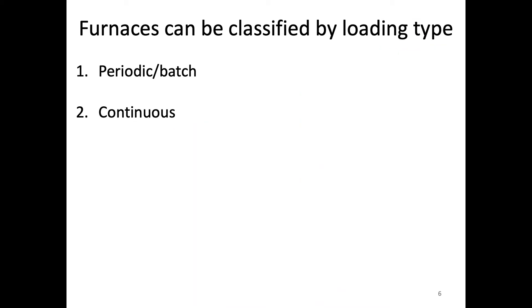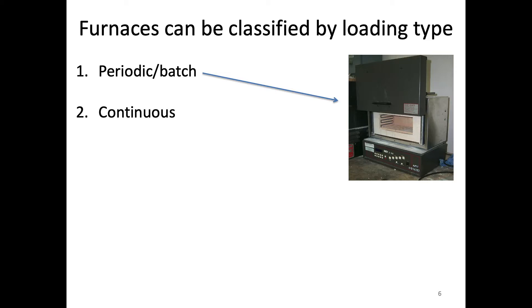Another way to classify these furnaces is by the loading type — how we actually load samples into them. The first type is periodic or batch, which is more common on a lab scale. Here I've shown a picture of a box furnace. We'd have a few ceramic parts we want to sinter, put them in the furnace, close it up, start the program, and when it's finished take them out and start over again as individual batches. This is useful on the lab side where we're probably making small quantities, but on the industrial scale this is not usually the best way to make large quantities.